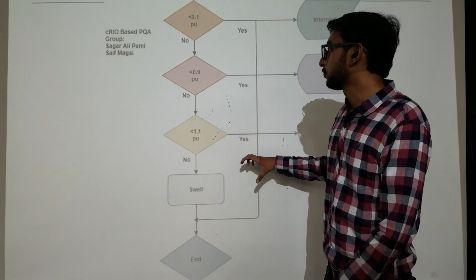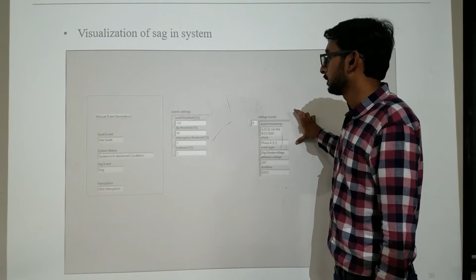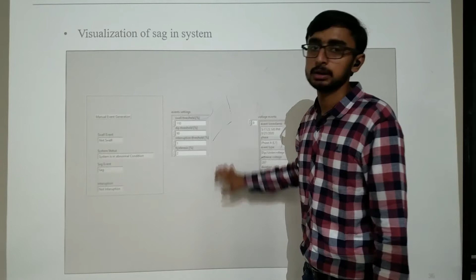This is basically the detection of our sag events. As you can see, there is a manual event generation, where manual limits are defined by us, and this is a predefined block of sag detection. These are the limits of IEC 61000 that we follow in our detection.